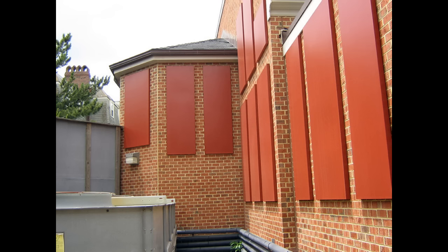On the right side, on the building itself, those appear to be perforated metal panels set at fairly close distances to each other to absorb the reflected sound. Otherwise, that noise would reflect off the building, over the fence, and continue to bother the neighbors.